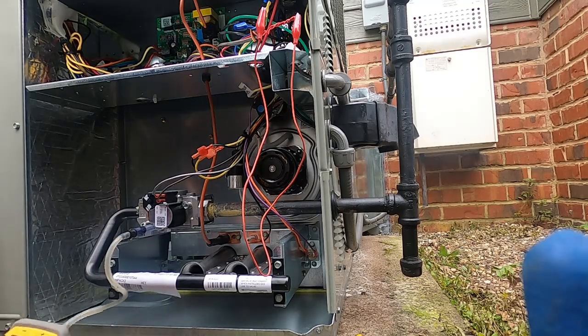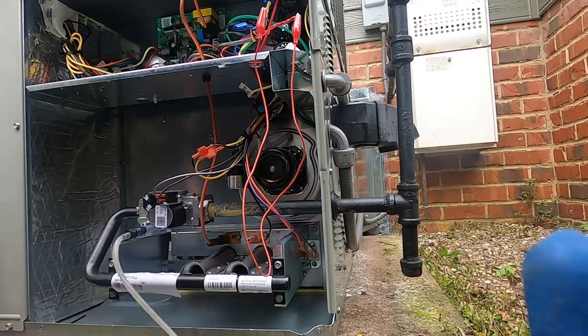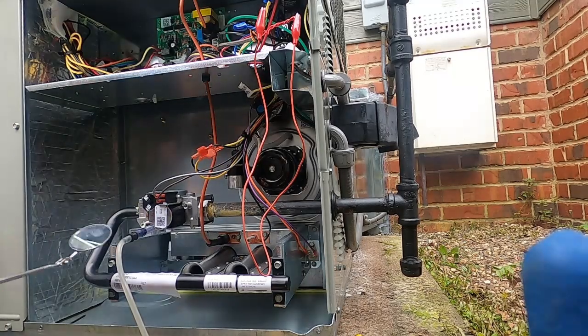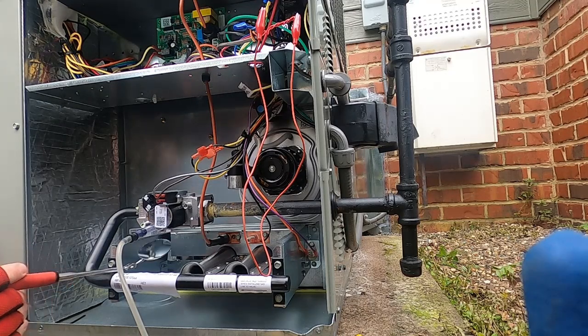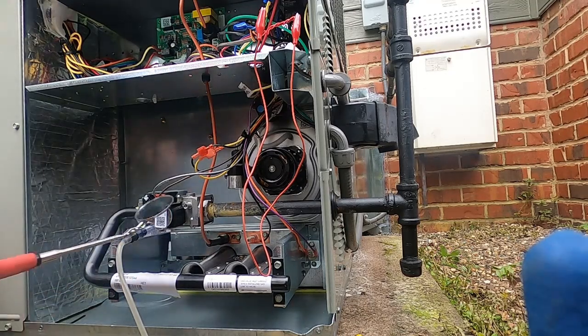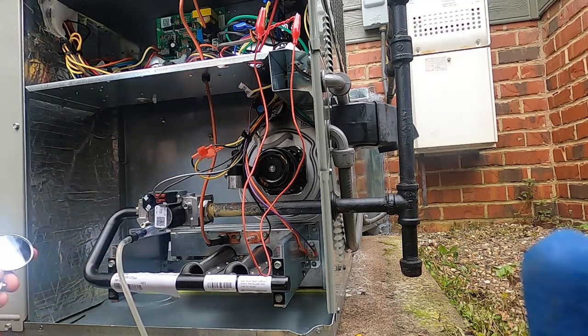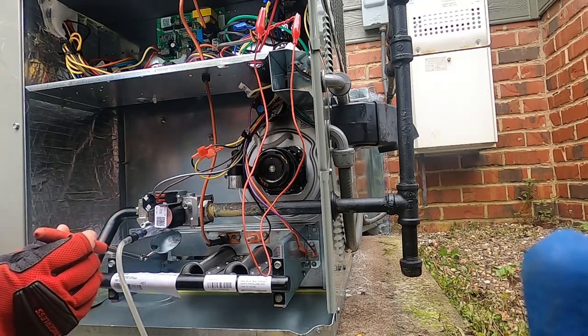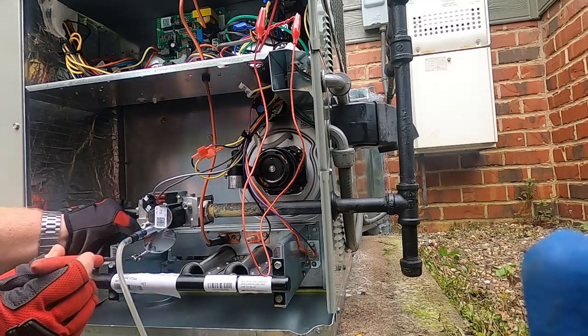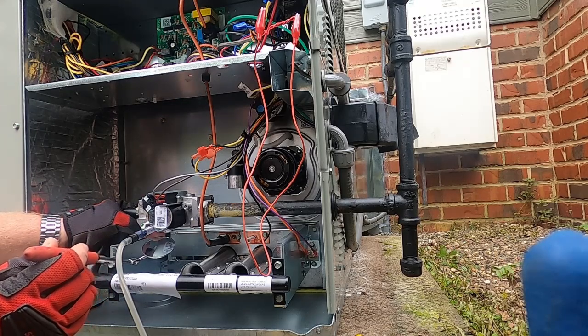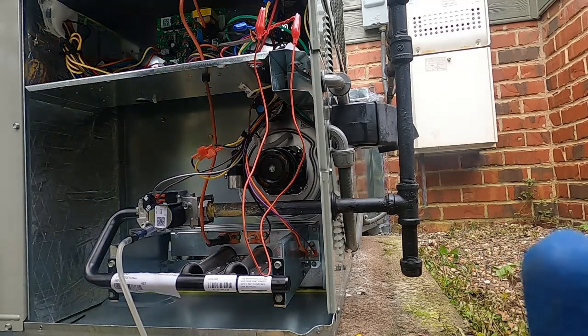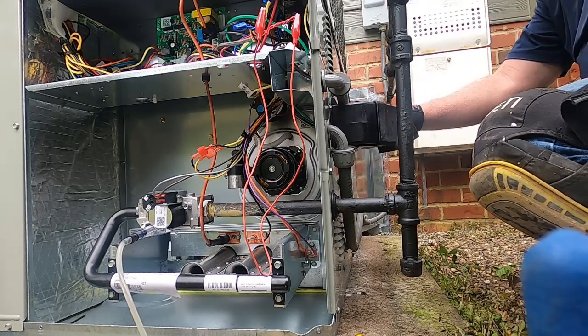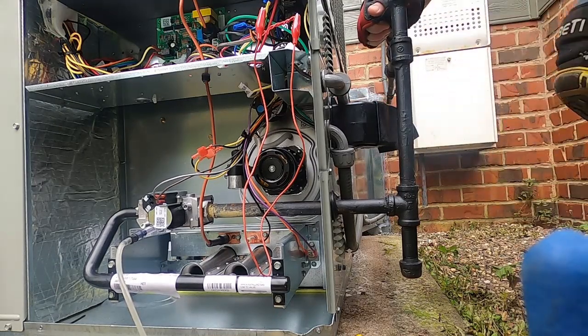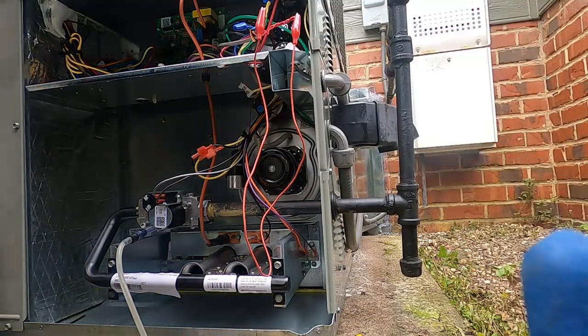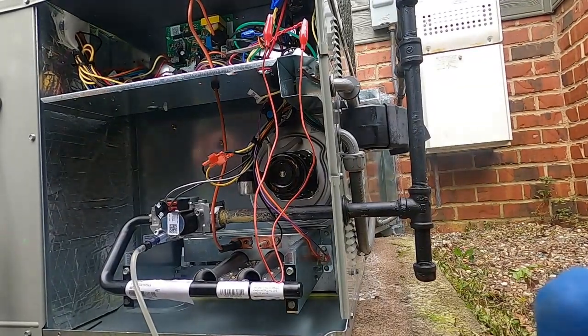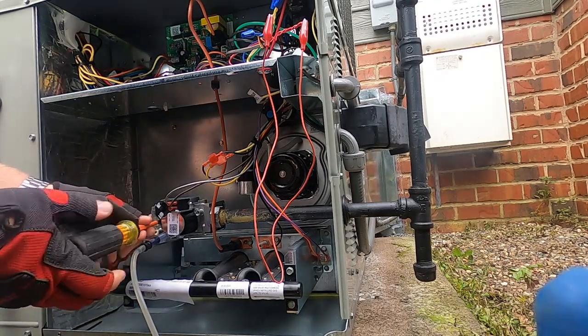So our gas pressure is 3.5. I typically will use the sticker on the side of the gas valve, which is so hard to read. It's the smallest print. It'll tell you on the side of the unit 3.3 or 3.5, but I like to typically see what the gas valve says on it. And that's going to say 3.3. See what the sticker says. Sticker also says 3.3. So I am going to set this gas pressure back down to 3.3.